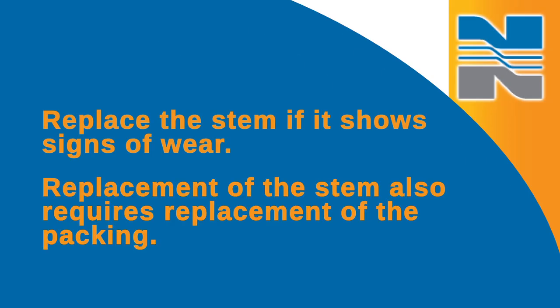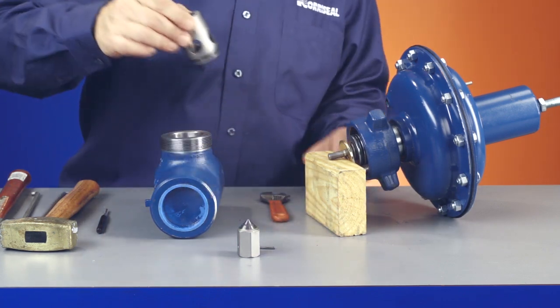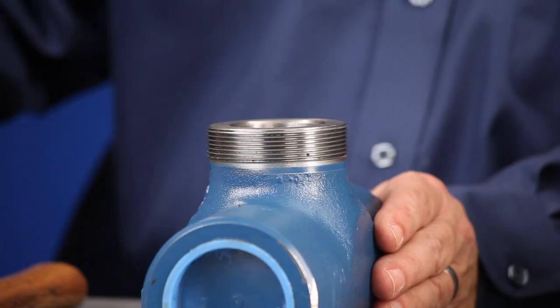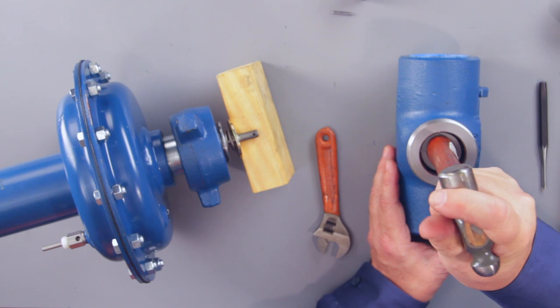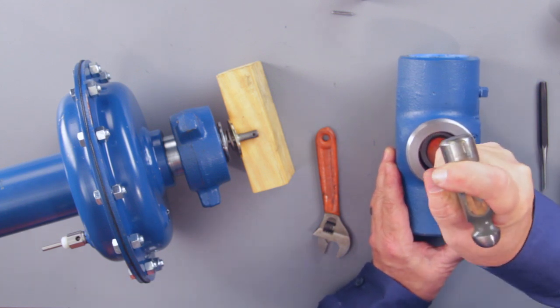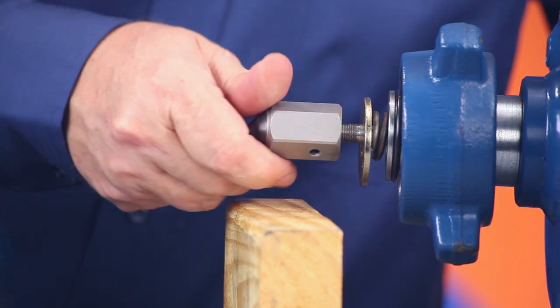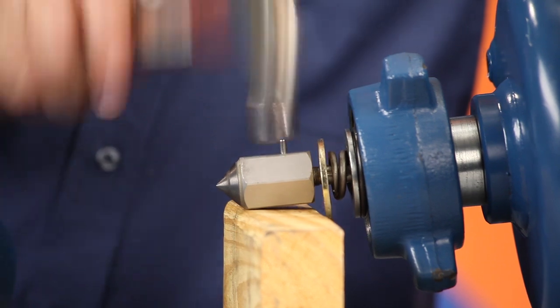Replacement of the stem also requires replacement of the packing. After you've replaced the packing correctly, it's time to reassemble the trim. To do this, you'll need to attach the plug to the stem and insert the seat back into the valve body. Finally, you'll reassemble the valve by reversing the order of disassembly.